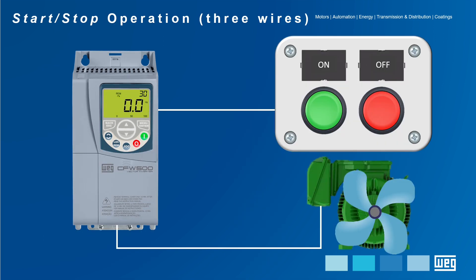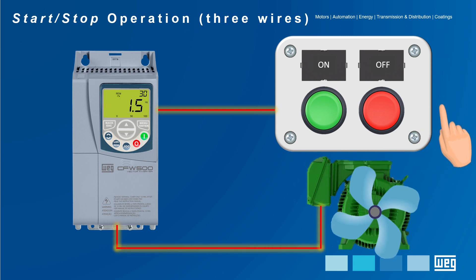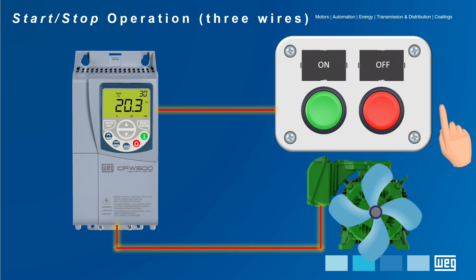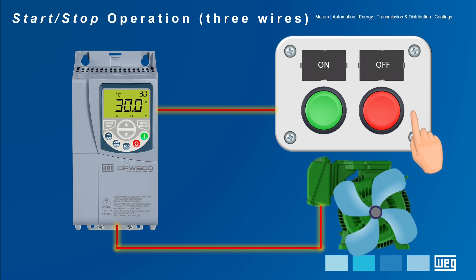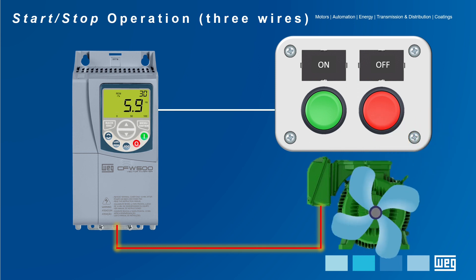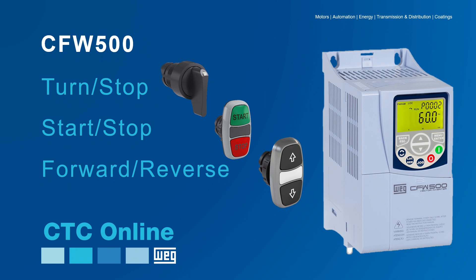In this operation representation it can be observed that a PULSE on the ON button is enough for the drive to start the motor without the need for external accessories to keep the motor in operation. To turn it off, all that is needed is a PULSE on the OFF button so the normally closed contact opens and the drive turns the motor off respecting the deceleration ramp.